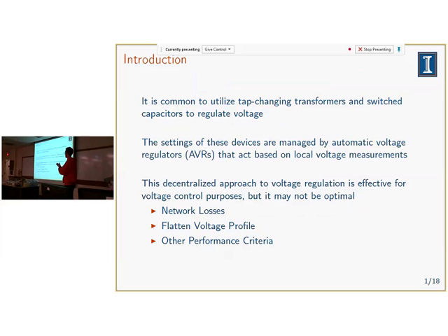In distribution systems, it's common to utilize tap-changing transformers and switch capacitors in order to regulate voltage. A lot of times these devices are managed by automatic voltage regulators, which act based on local measurements. This could be either on the secondary side, or some sort of measurement on a local bus, or a nearby bus. They could even be controlled manually.